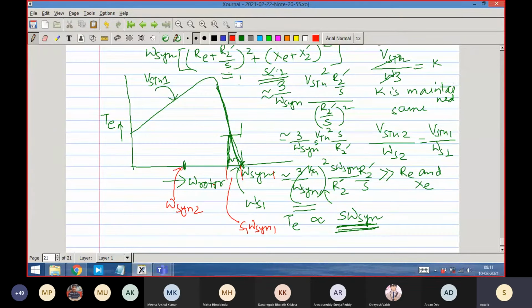Physically, you remember the expression of the induced voltage. It has a frequency term, because after doing N d phi by dt, the frequency term comes after the derivative. So induced voltage is proportional to frequency. So if I had not changed the voltage but reduced the frequency, it would have been producing more flux. In order to maintain the same voltage, the flux had to go higher, right?